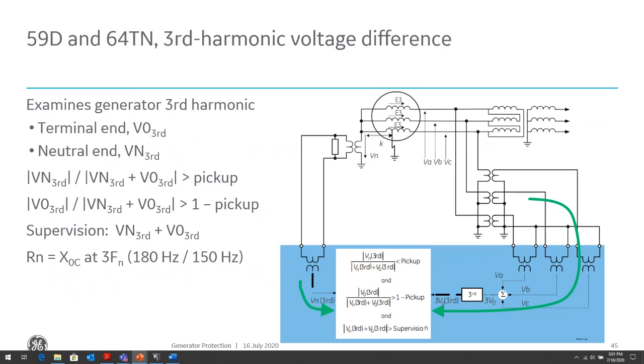The 59D/64TN element responds to third harmonic voltage measured at a generator neutral and the generator output terminals. When used in conjunction with the neutral overvoltage element, which is the fundamental element, the 59N, it provides 100% ground fault protection of the stator windings. The amount of third harmonic voltage that appears in the neutral is both load and machine dependent, as I mentioned. Therefore, this method is more reliable, where it's more adaptive to being able to not have to block this element during certain operating conditions of the machine.